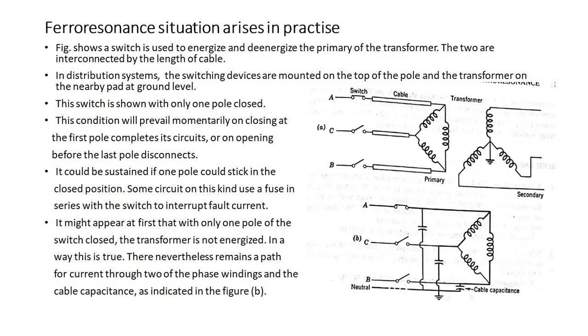Some circuits make use of a fuse in series with the switch to interrupt fault current. It might appear at first that with only one pole of the switch closed, the transformer is not energized. In a way, this is true. There remains a path for current flow, through two of the phase windings and the cable capacitance and inductance in the figure. This current can produce resonance and impose excessive voltage across the transformer and the cables on the unenergized phases. At that instant the lightning arrester connected to B and C phases of the transformer is operated. If the condition is sustained, repeated operation can destroy the arresters.